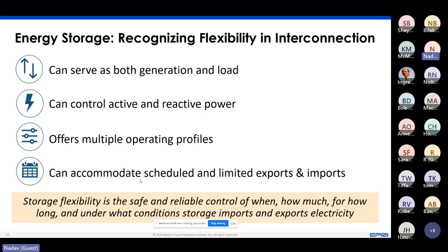Storage can control active and reactive power. It can modulate its absorption or injection of reactive power in relation to grid voltage, and it can also reduce active power to decrease voltage. So, in shorthand, these features can really help address grid instabilities and fluctuations in power quality. It offers multiple operating profiles and can be used by multiple customers or grid purposes. These various use cases speak to the versatility of storage, either being grid tied or islanded, and being used for a variety of purposes beneficial to the grid and to end use customers. And then finally, it can be designed to a schedule. That's a big deal, right? The amount and timing of power exports or imports can be controlled to help benefit the grid. So in that pink box here, what we're really talking about when we think about storage's flexibility is the safe and reliable capability to control when and how much storage imports and exports electricity, and whether those imports and exports are happening from the grid or to the grid, in coordination with maybe a co-located solar system or another generation and load source.